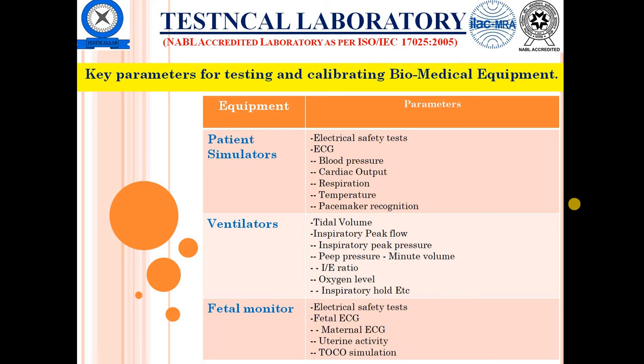calibration. Another one is the ventilator, a very vital clinical instrument. The life of the at-risk patient is maintained on this instrument, so it is a very critical instrument. And the tests we perform are EST, tidal volume, respiratory peak, inspiratory peak pressure, IE ratio, oxygen level, inspiratory hold, etc. And also, I think I missed the electrical safety test, that is paramount.